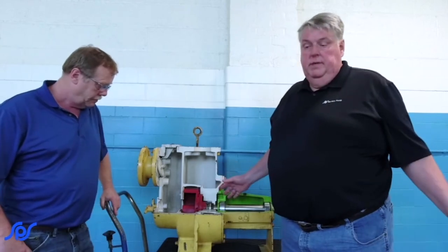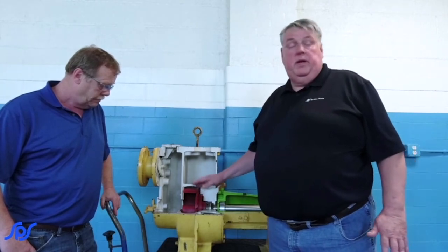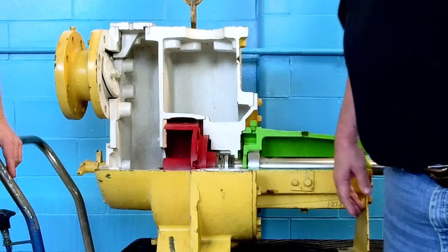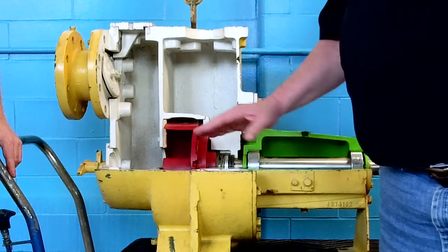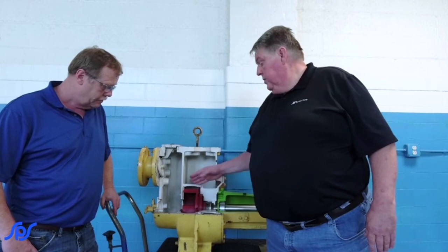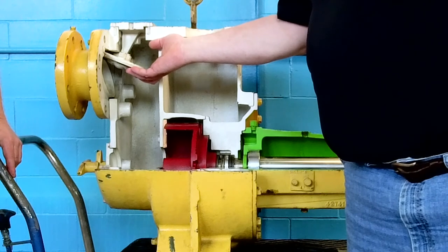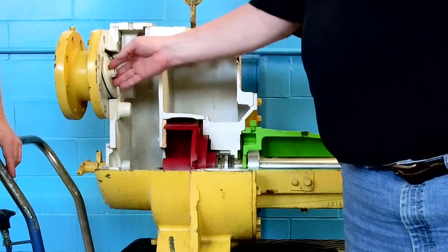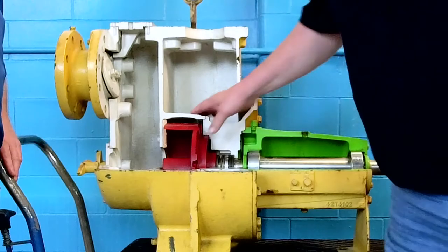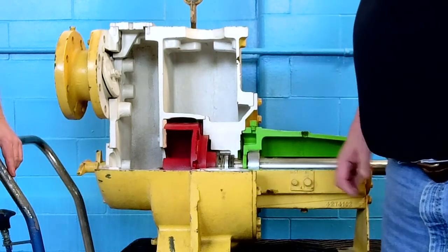We've got different types of impellers and you'll see different impellers depending on whatever the application may be. This particular one is a trash pump — an open vane trash pump that uses a wear plate on the front. This particular one is a self-primer that has a check valve on the suction side to help keep the cavity full of water when you're first initially priming it, and it has a cutwater area where the impeller comes in close to help evacuate the air out of the system.